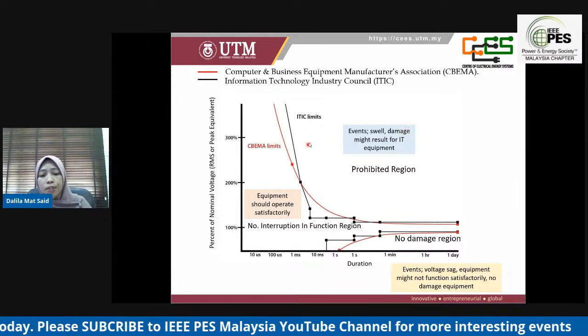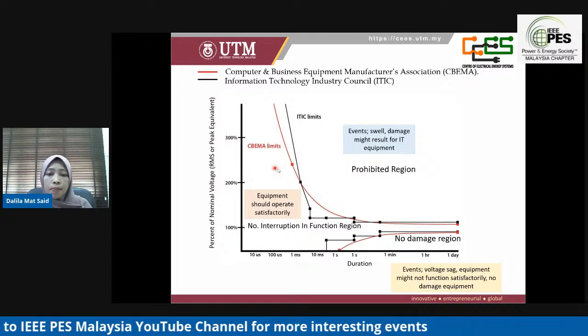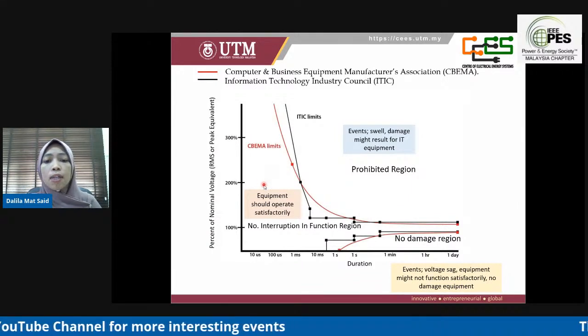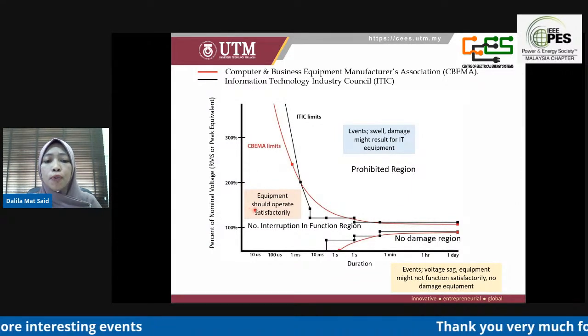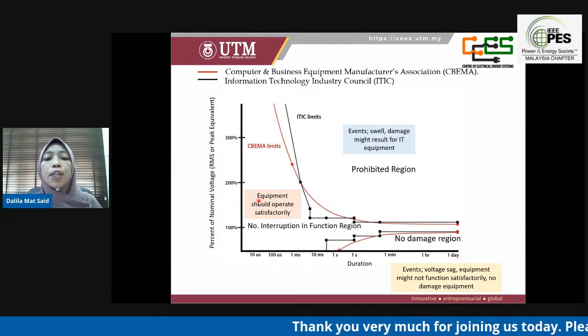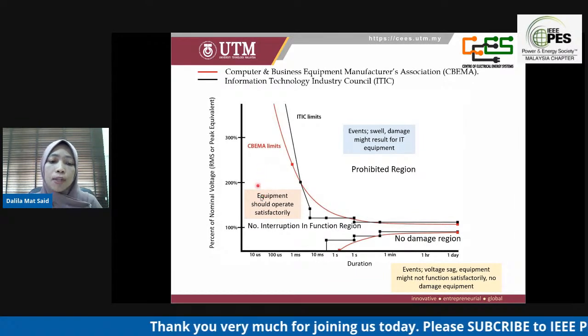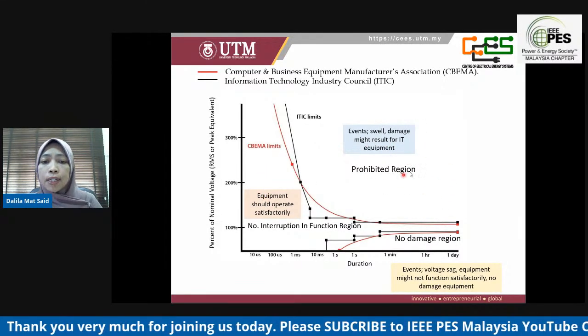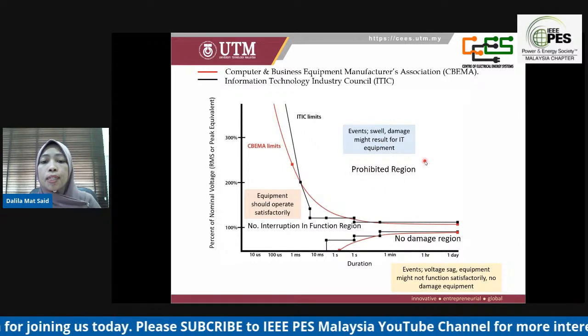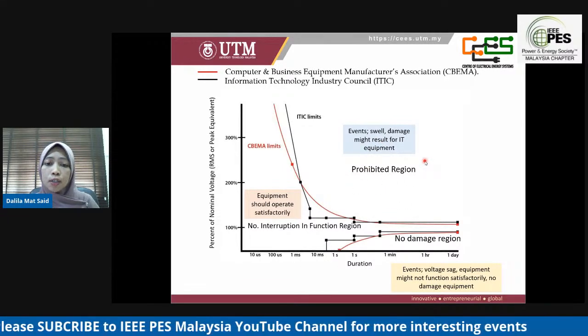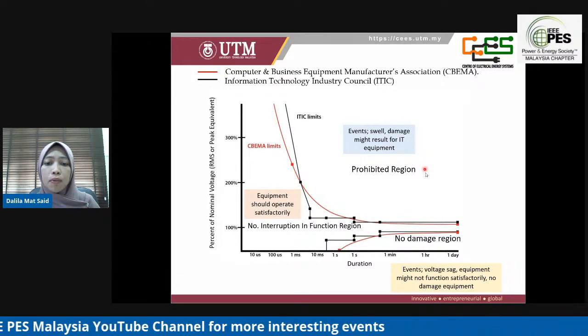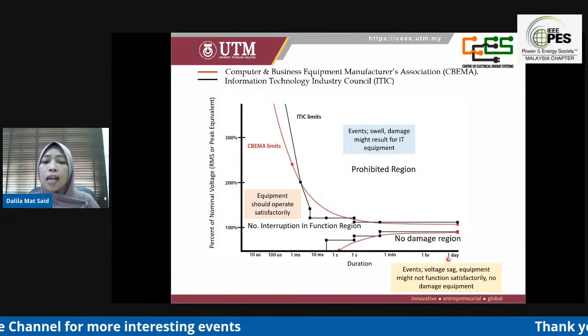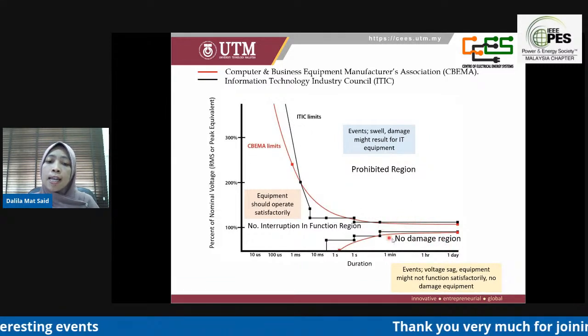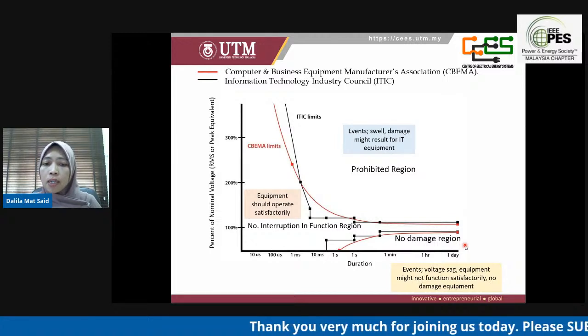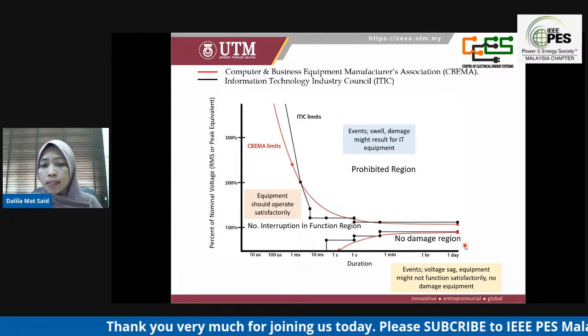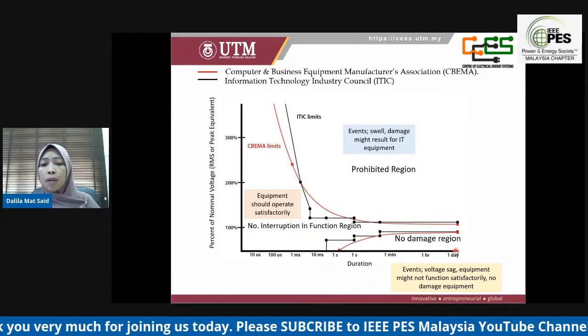Both curves have three regions, where the first region we can call the no interruption in function region. This means that if you have an event in this region, equipment should operate satisfactorily. The second region is the prohibited region. For this prohibited region, events such as surges may cause damage to IT equipment. And the third region we can classify as the no damage region, where if an event such as a voltage sag occurs, the equipment may malfunction.